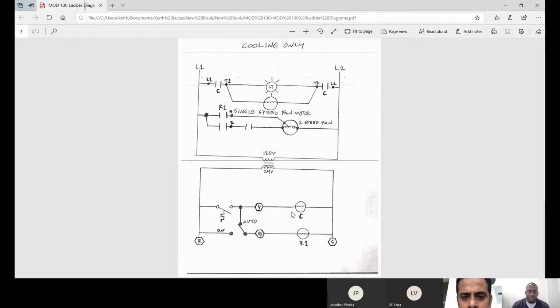Down here in our low voltage section, we have a C again. This is our contactor coil. And then we're going to be using Y, which is our cooling circuit, and we're going to be using G, which is the fan. So there's a switch on our thermostat that I think we might have talked about, our fan switch. It has auto and it has on. And that's what you see right here in the diagram, auto or on.